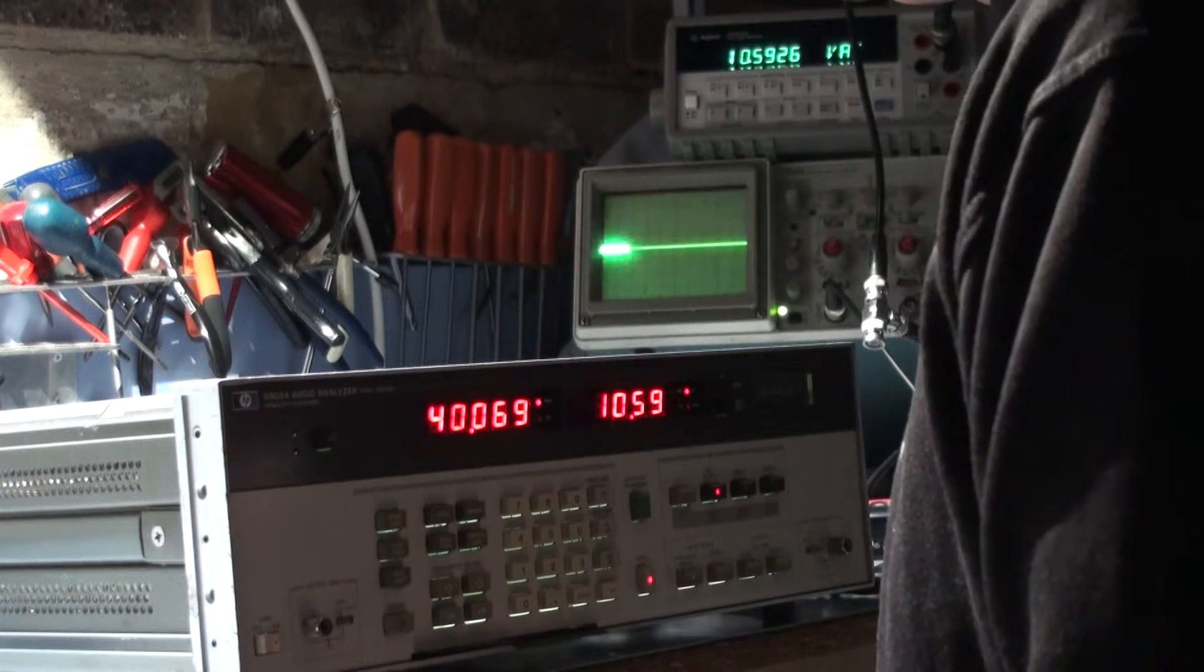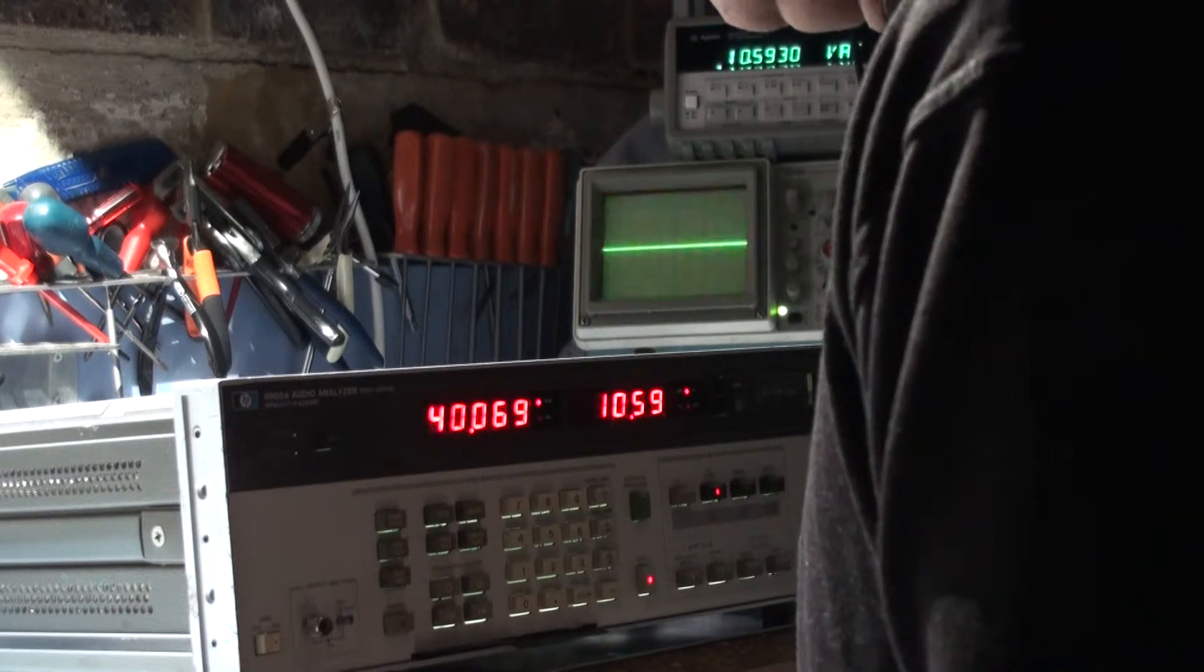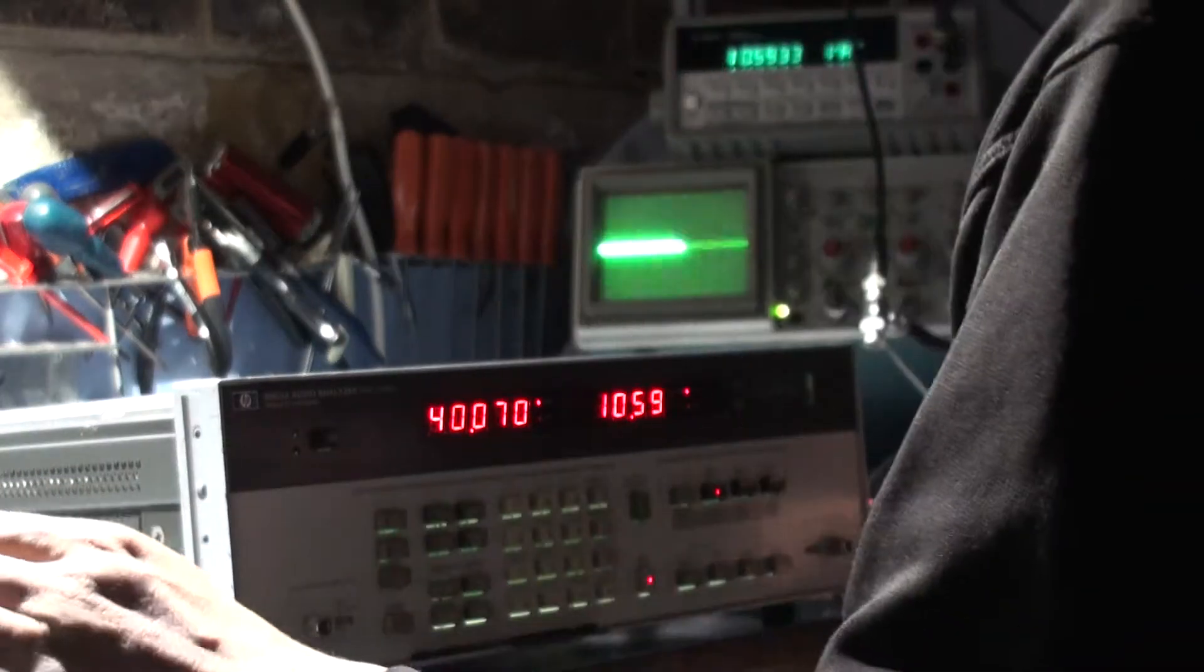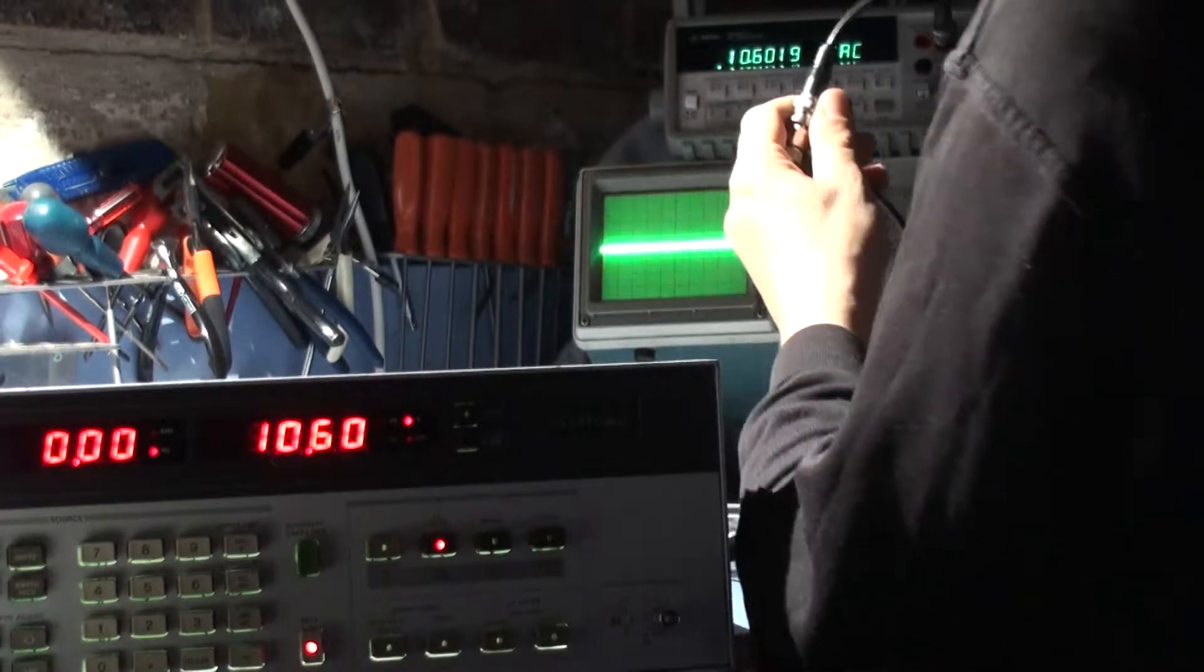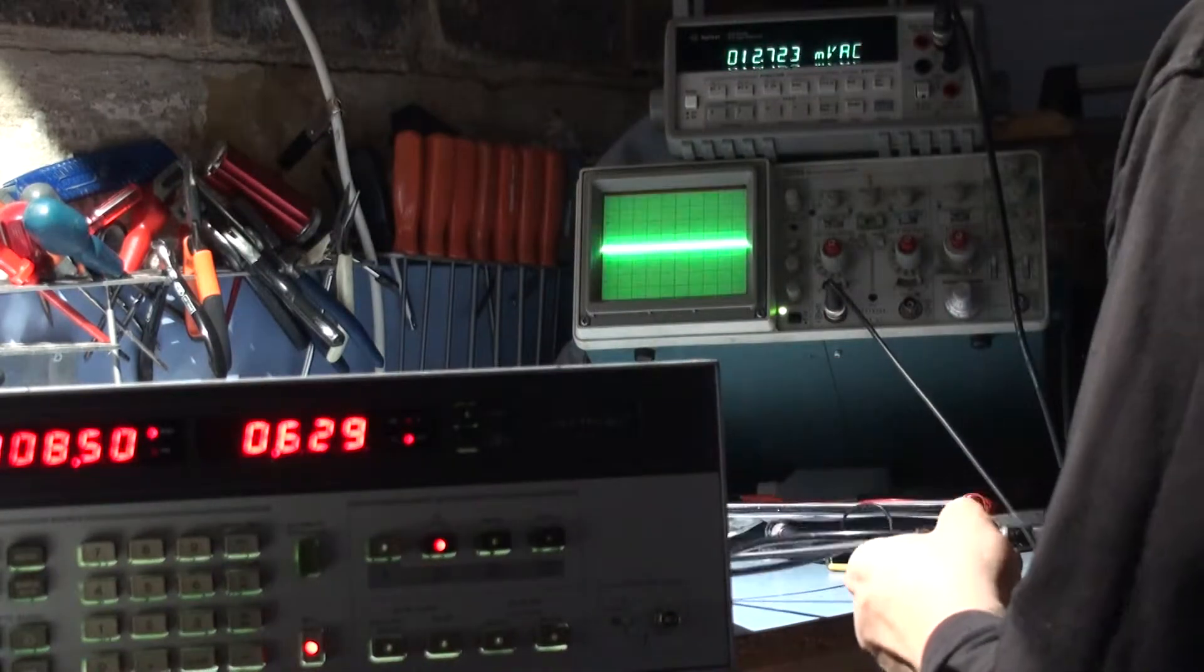And then the next step is common mode rejection adjustment. And what it says is you connect the high output of the generator to the low and the high input. So the low and the high inputs are joined up together. So let's do that. We shouldn't need that anymore. I'll leave it on just in case.